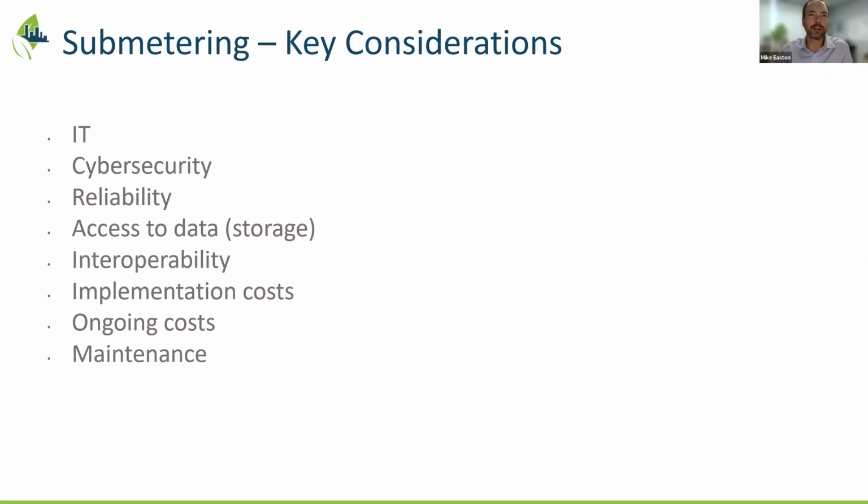Yeah, thanks, Frank. I'll try and touch on IT and data collection issues first. If you remember the slide a few ago, it showed data going to both a web-based solution and an on-site solution like the building automation system. So you can do one or the other, you can do both. And really it's up to the project or the property management and operations team to decide what they want. If you're going to be doing an on-site integration, the most important thing is that you standardize the protocols that are going to be used.